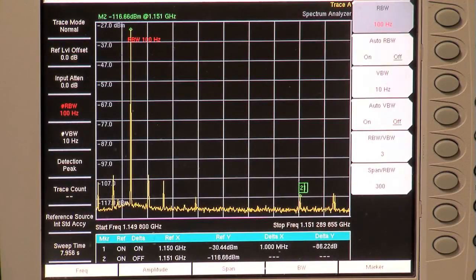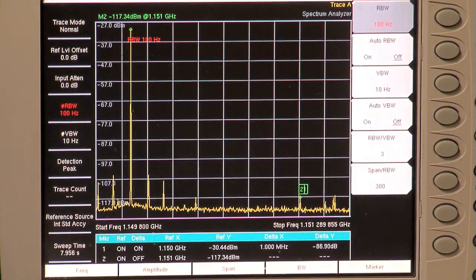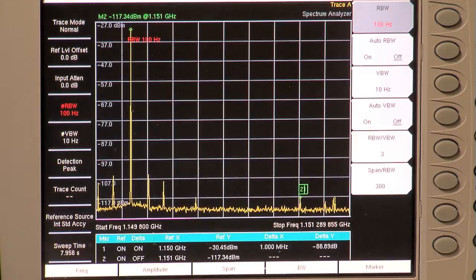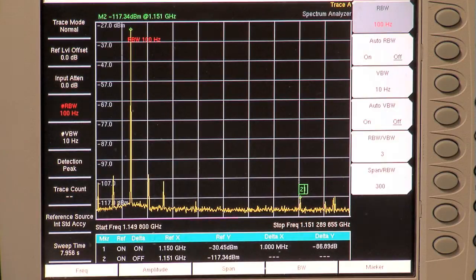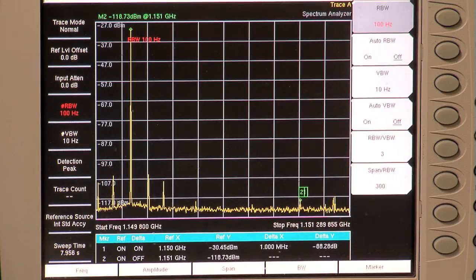Dynamic range is one of the fundamental specifications of a spectrum analyzer and at the same time one of the least understood. Dynamic range is a measure of the ability of an instrument to measure a tiny signal in the presence of a gigantic signal.